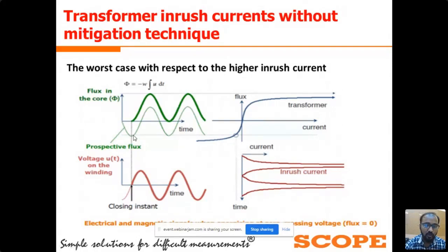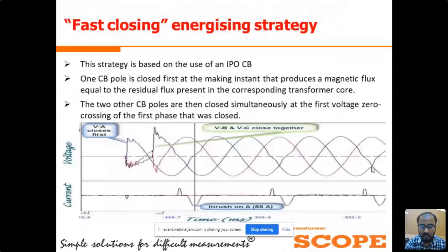And again, if we try to close the power transformer near the voltage 0 instant, means again we are trying to add the 1 pu flux in the power transformer. Due to that, there will be a chance of saturation of the transformer iron core, and the transformer core will take the highest inrush current for the magnetizing. You can see here, if we switch the power transformer at this moment, the transformer will take the highest inrush current at this moment. So this is the worst case with respect to the highest inrush current for the power transformer application. So with the control switching device, we are trying to avoid these things.